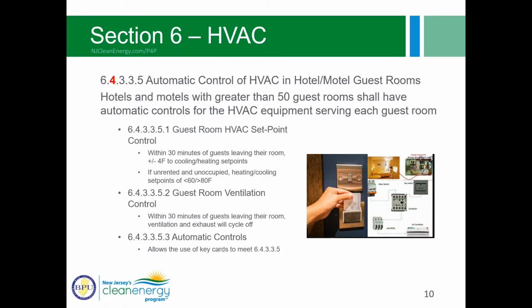For the HVAC section here, again, this one is going to be in the mandatory section, where this addresses the automatic control of HVAC in hotel and motel guest rooms. For those buildings that have greater than 50 guest rooms, they're looking to have controls for the HVAC. What these controls will do is adjust the set points up or down after the guests vacate their room, or if a room is not occupied or not rented for some extended period of time, those set points are set even further out of range until they are occupied by the guests. And the automatic controls that they're referencing do allow the use of key cards.